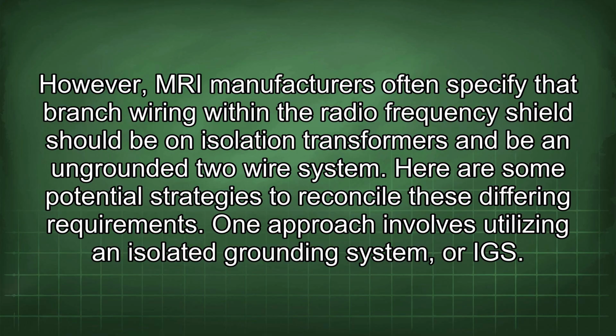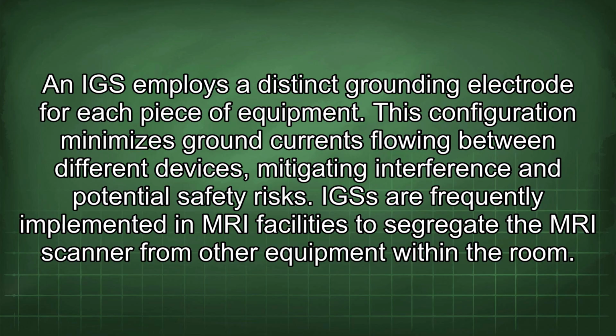Here are some potential strategies to reconcile these differing requirements. One approach involves utilizing an isolated grounding system, or IGS. An IGS employs a distinct grounding electrode for each piece of equipment. This configuration minimizes ground currents flowing between different devices, mitigating interference and potential safety risks. IGS are frequently implemented in MRI facilities to segregate the MRI scanner from other equipment within the room.